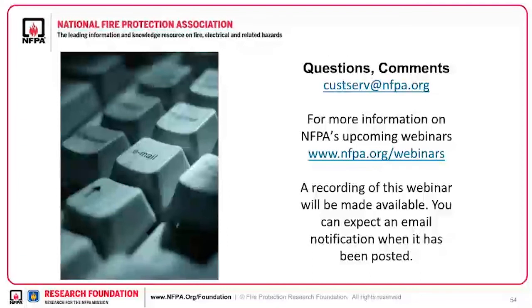Next question, are you sure the target rack fire is heat related and not short circuit related from the water? And we talked about that a little bit during the presentation. I certainly can't discount that short circuit could have also been an issue. But we have temperature data during the test that shows that some of the modules in the target rack during the NMC test were becoming elevated. So that would lead me to believe that it is at least partly related to the fire, but I certainly couldn't discount that the water intrusion was contributing.